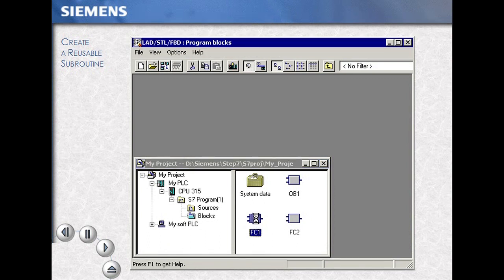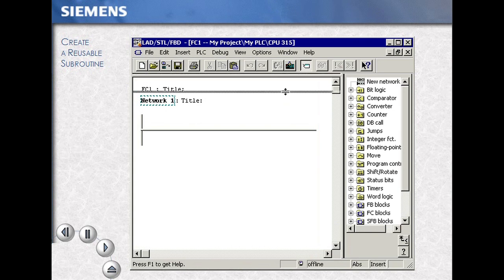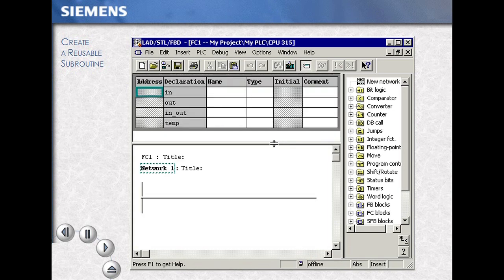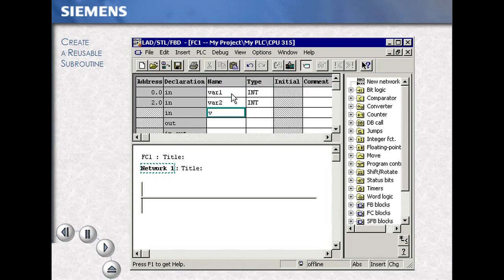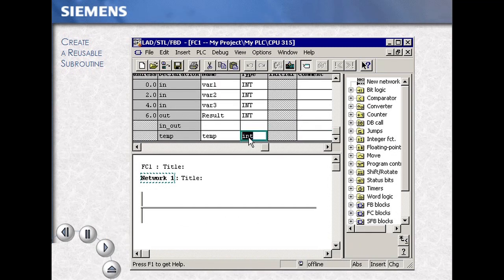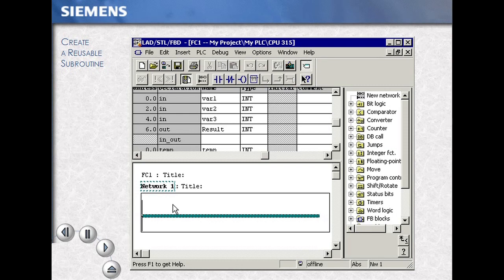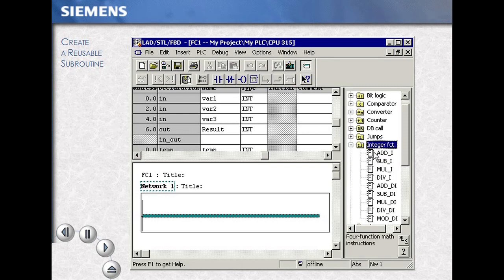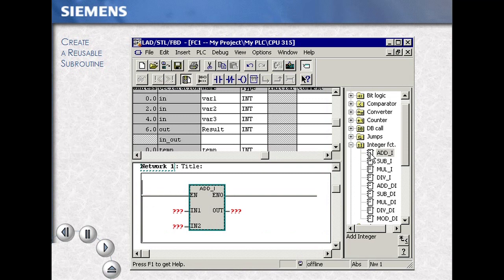Double clicking our block opens the block into the program editor. To expand and view the local variable area, we slide the window. We then begin to enter our local variables — in this case variable 1 as an integer. As we continue, we enter several variables as integers. We also choose a result as an output, and include temporary variables. These variables are to be used within our code section.